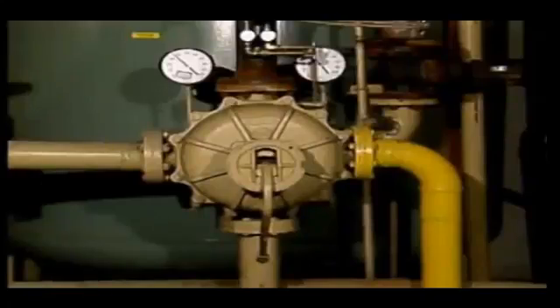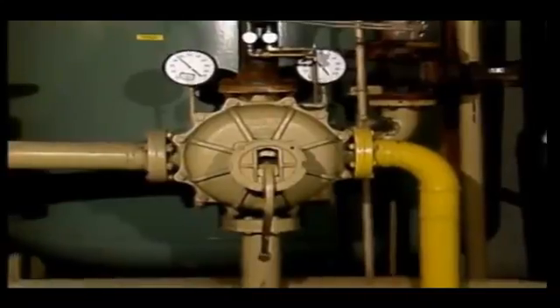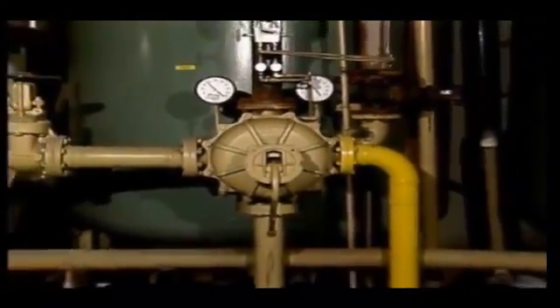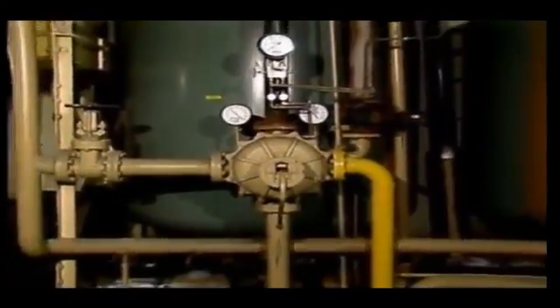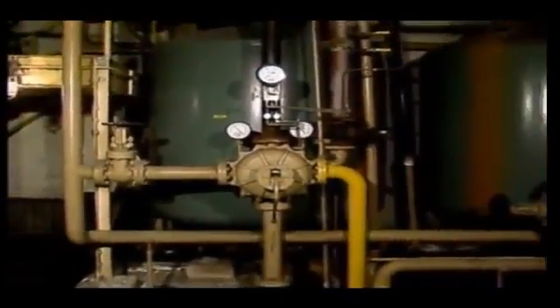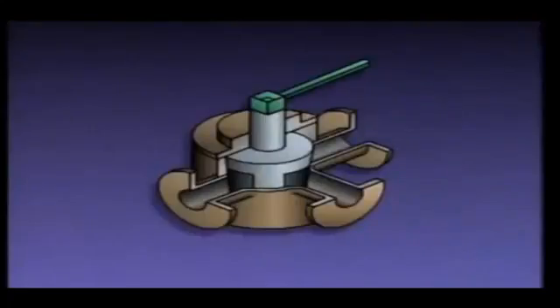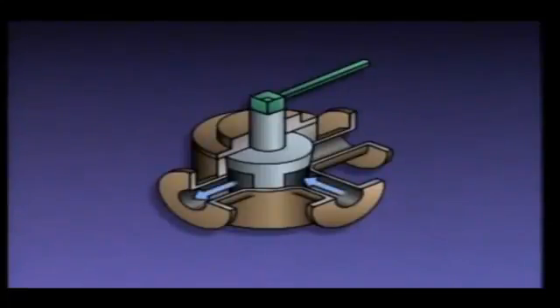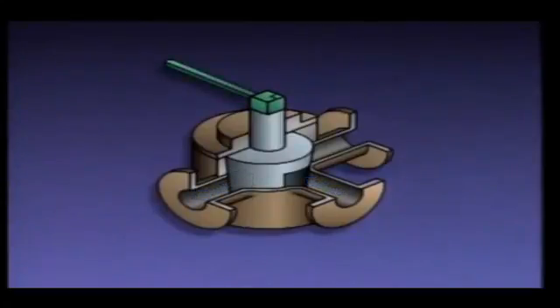Now let's look at another type of plug valve: the multi-port plug valve. A multi-port plug valve has additional piping connections and a different type of plug. Instead of an opening that allows fluid to pass straight through, a multi-port plug has an L-shaped opening. Here's an example of a three-way multi-port plug valve. When the plug is lined up in one position, fluid enters here and exits here; when moved to another position, it exits through a different port.